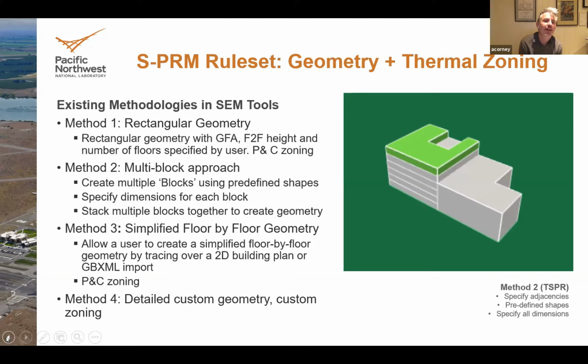Then it's almost even more of a difference, because especially if those systems don't modulate very well, with a single zone per floor you've got a fairly constant load - the sun goes around the building and comes in at one facade, but you've got a big internal load driving it. If you have perimeter zones and a core zone, each with their own zone unit, those are going to have a big fluctuation in load versus the peak.